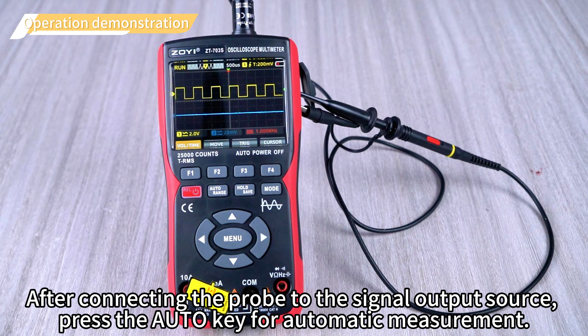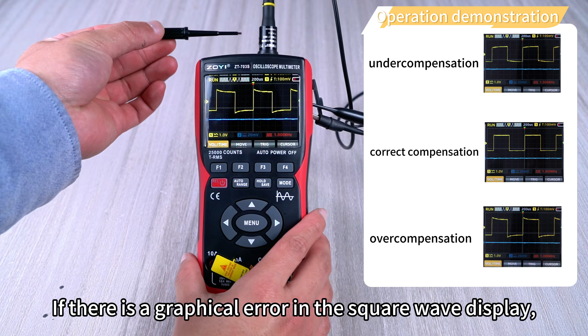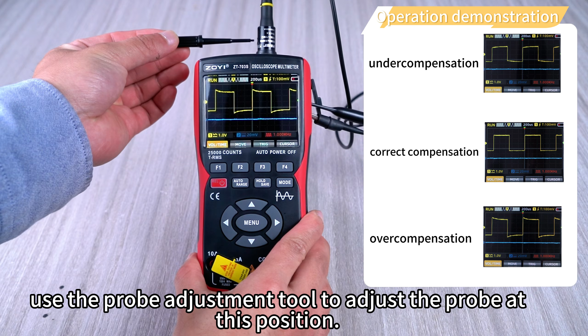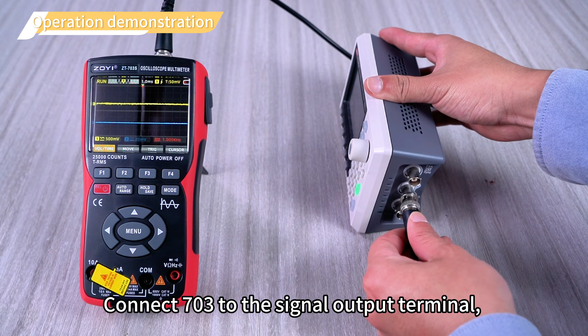After connecting the probe to the signal output source, press the Auto key for automatic measurement. If there is a graphical error in the square wave display, use the probe adjustment tool to adjust the probe at this position. Connect 703 to the signal output terminal.